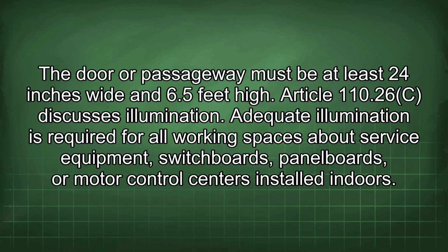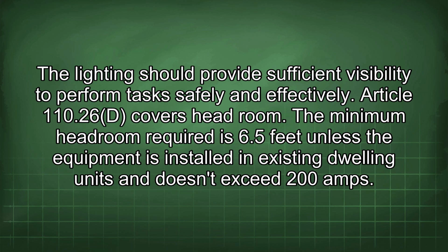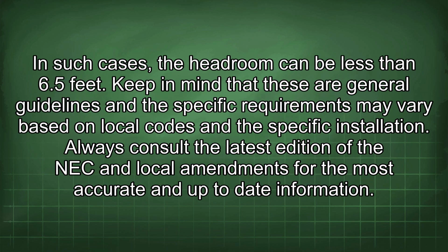Article 110.26(C) discusses illumination. Adequate illumination is required for all working spaces about service equipment, switchboards, panelboards, or motor control centers installed indoors. The lighting should provide sufficient visibility to perform tasks safely and effectively. Article 110.26(D) covers headroom. The minimum headroom required is 6.5 feet unless the equipment is installed in existing dwelling units and doesn't exceed 200 amps. In such cases, the headroom can be less than 6.5 feet.